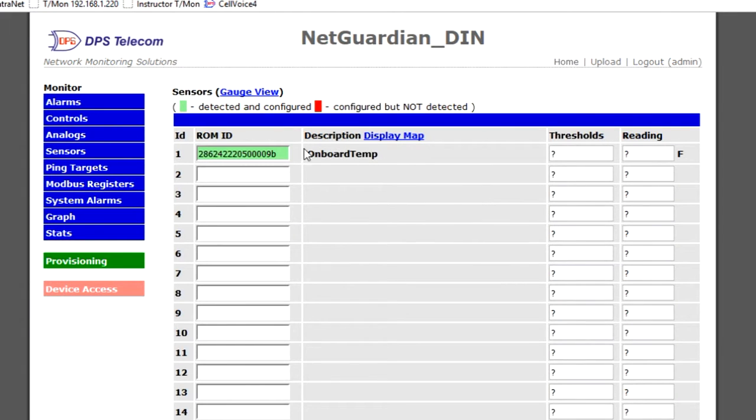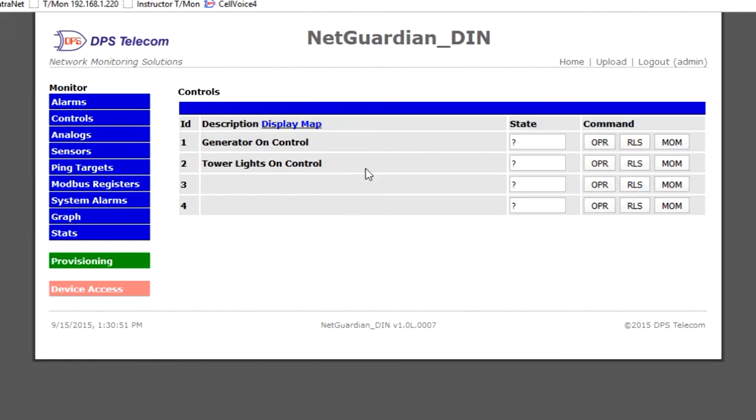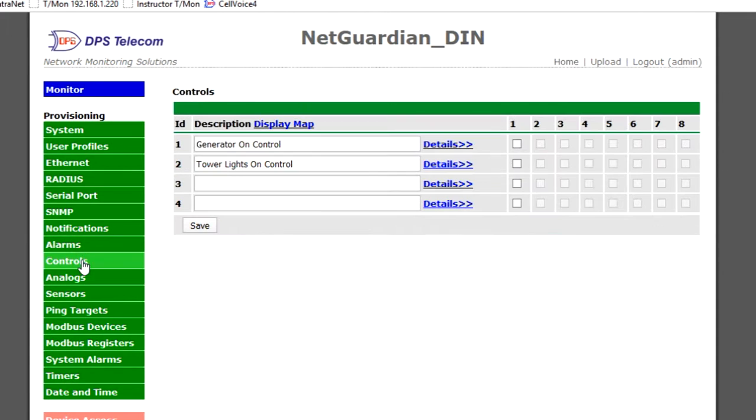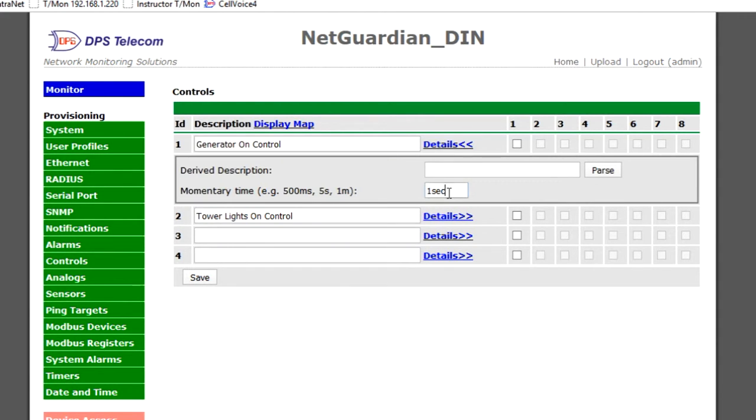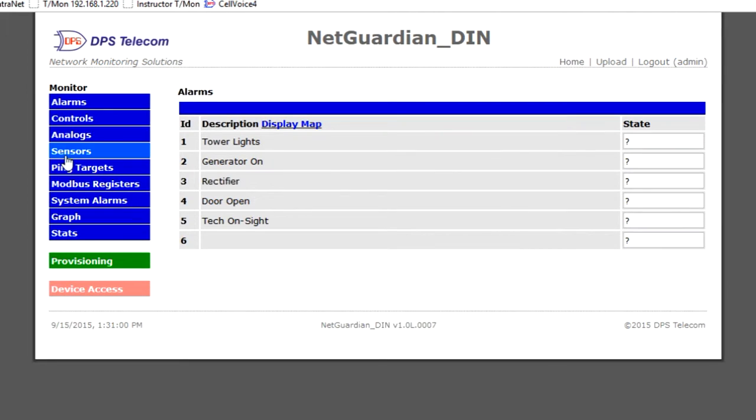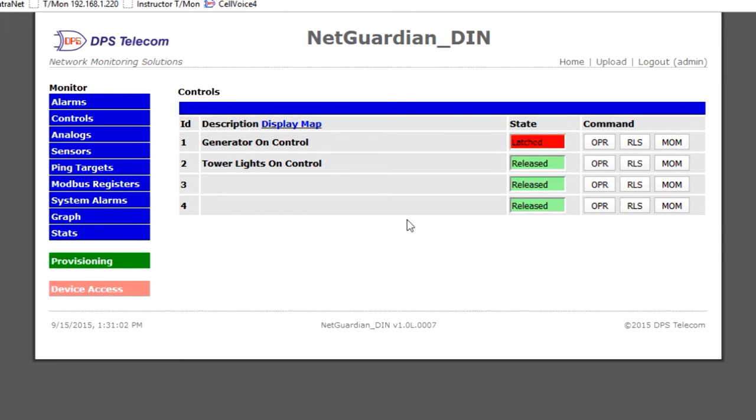Oh, just one quick question on that momentary. Is that adjustable, or is it fixed? Yeah, so I'll go over that, but you have a time duration for that momentary. Is momentary bidirectional, so if it's latched and your momentary doesn't release and latch again? Well, it depends on either the jumper, if it's a form A, or the wiring if it's form C. So it'll be normally open or normally closed depending on how it's set up. And then obviously it'll switch states on that momentary.